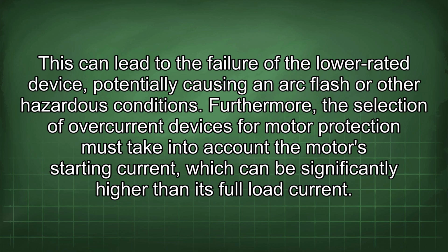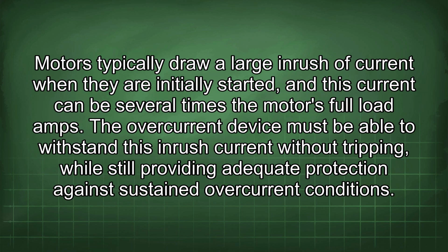Furthermore, the selection of overcurrent devices for motor protection must take into account the motor's starting current, which can be significantly higher than its full load current. Motors typically draw a large inrush of current when they are initially started, and this current can be several times the motor's full load amps. The overcurrent device must be able to withstand this inrush current without tripping, while still providing adequate protection against sustained overcurrent conditions.